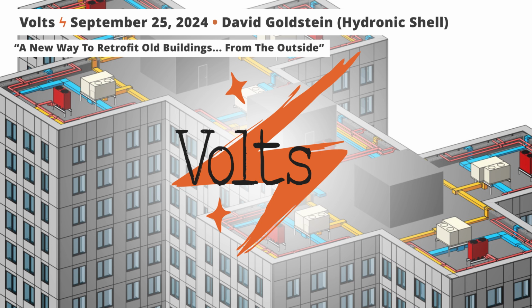The other perspective is that multifamily buildings tend to have small internal loads. If you look at the cooling load of a building, you have the envelope, exterior loads like sun coming in and heat conducting through the wall, those are your perimeter loads. When you super insulate a building, you can bring those way down. But you still have internal loads in the space, things like lighting, people, your computer and TV plugged in, ordinary appliances rather than commercial machines in a multifamily building. So internal heat gains in a multifamily building are relatively low, and once you super insulate the facade, overall loads can be very, very low.